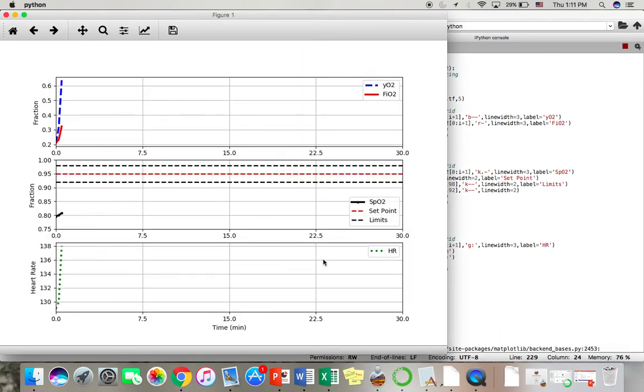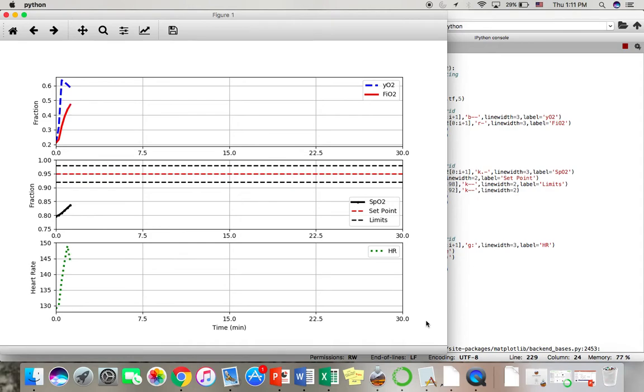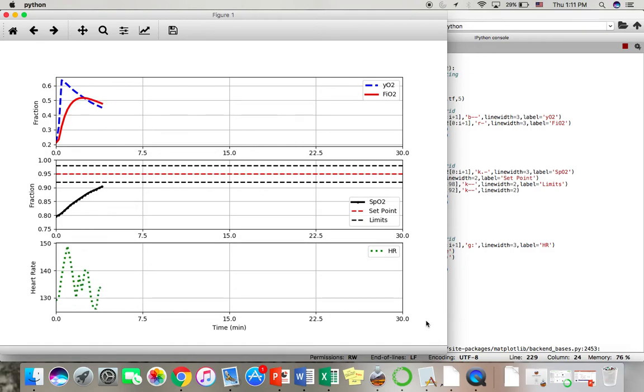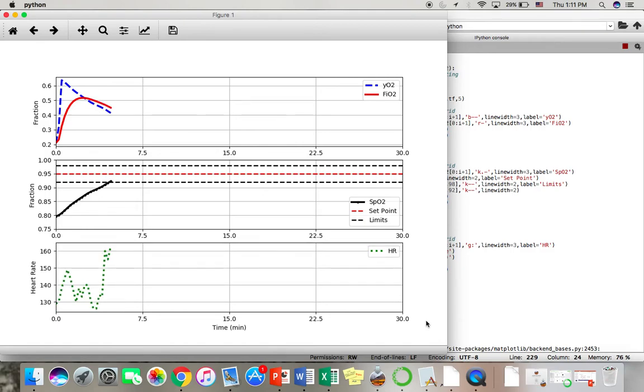And what we're looking at is a baby that starts initially, if we're walking this black line, initially at respiratory distress. Their SpO2 is below the healthy level. We adjust that by increasing the amount of oxygen that we're flowing into the incubator, the concentration.